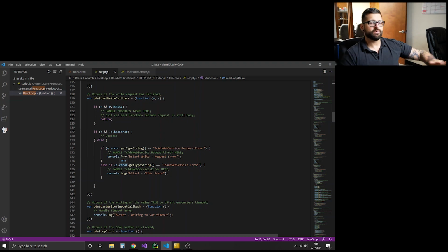And this is where, in a real visualization or real SCADA system, you'd want to program all of your error handling, all of your corner cases where something's gone wrong. That's largely abstracted in traditional HMIs and traditional SCADA systems, where you're working inside of a larger model made by an OEM. All this stuff is handled in the background for you. But when you're directly creating these communication pathways, you have to program yourself all of the corner cases and the exceptions that you need handled. Because if not, there's nothing else that's going to tell the program what to do.